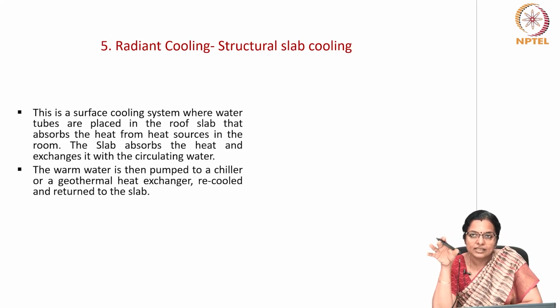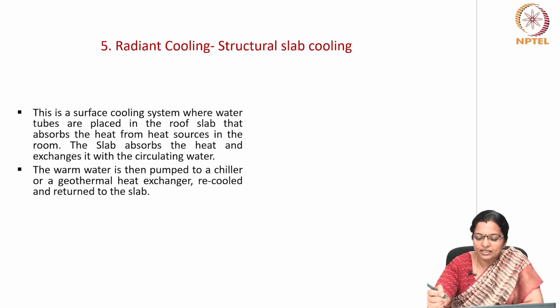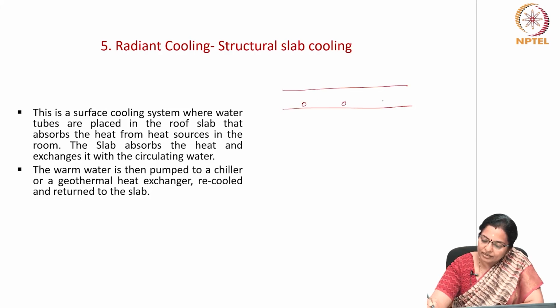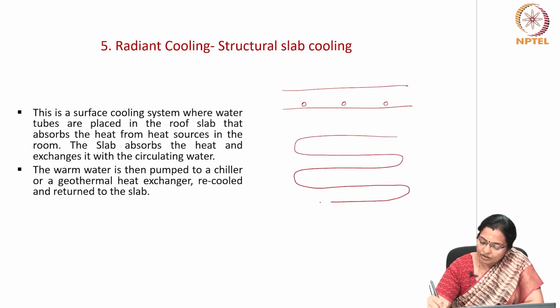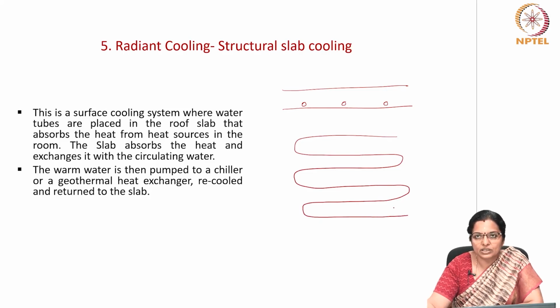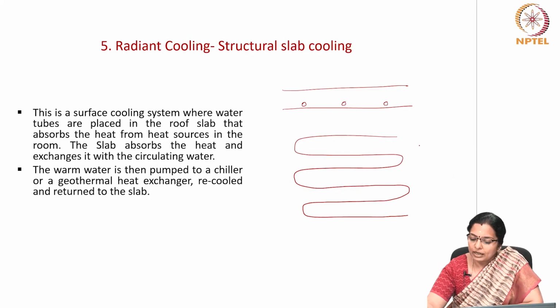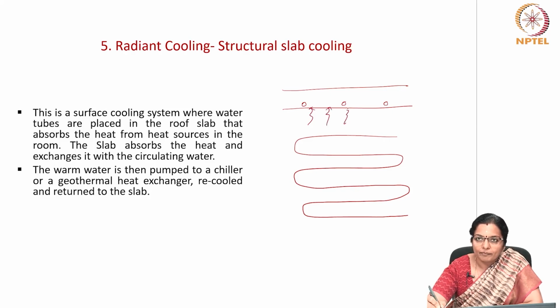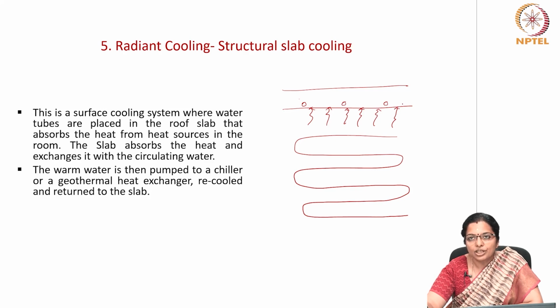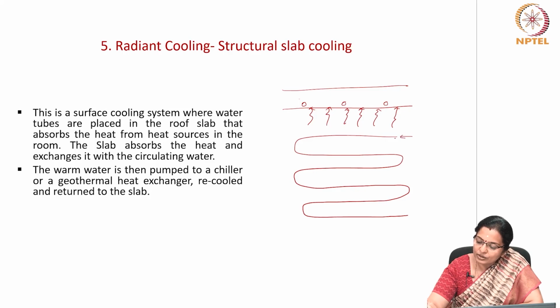So, this is a surface cooling system where water tubes are placed in the roof slab in section. This is how it looks, and the pipes are laid all along the roof and the floor slabs, and then the heat from the heat source of the room is radiated, and the slab absorbs the heat and exchanges it with the circulating tube in which chilled water is placed. So, the warm water is then pumped to a chiller or a geothermal heat exchanger, recooled and then returned to the slab.